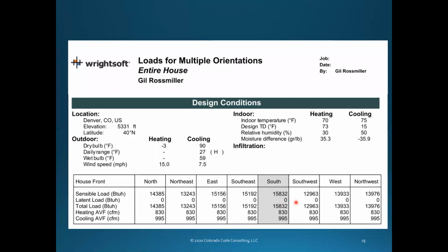They only make air conditioning equipment in half-ton increments, so that's 6,000 BTU. The difference between the worst and best is well within that, so we're probably in good shape. We don't need another design, and we certainly don't need another piece of equipment, because there isn't equipment available that fine-tuned. The only thing that might work is mini splits, but that's a whole different conversation.